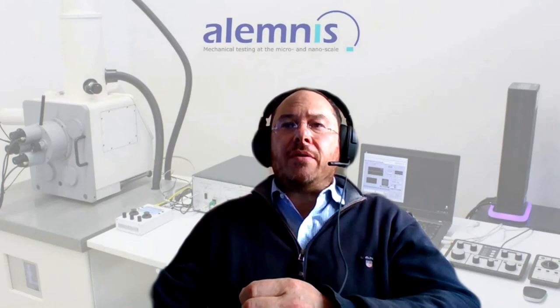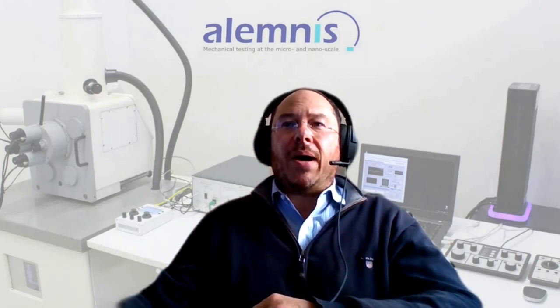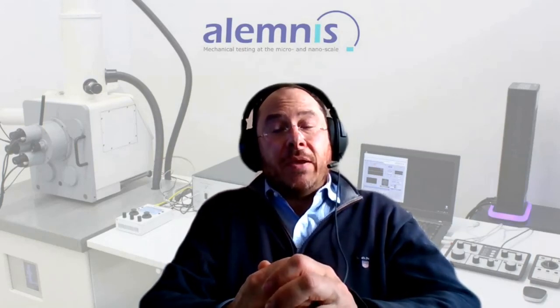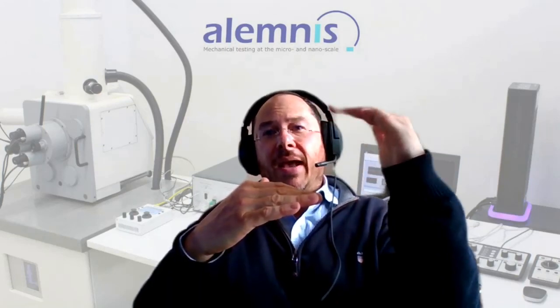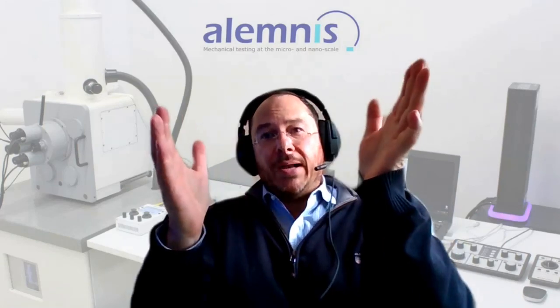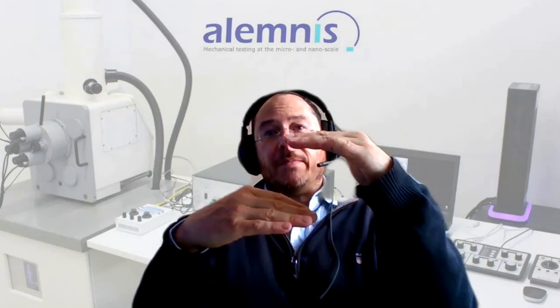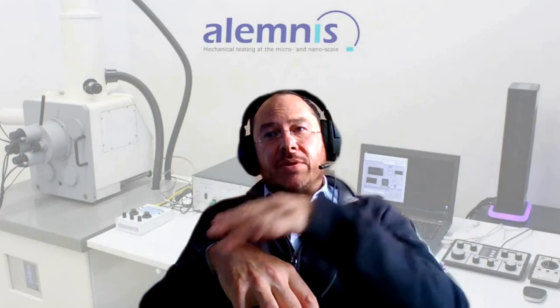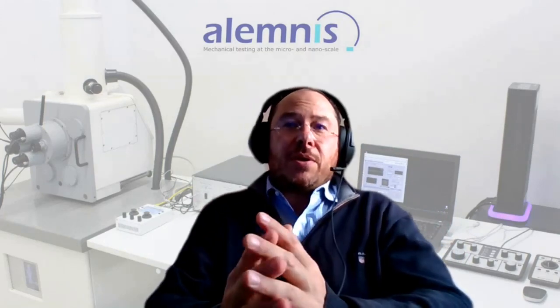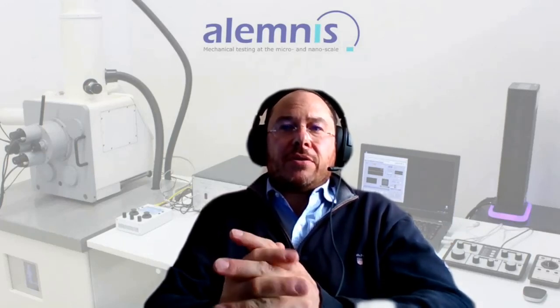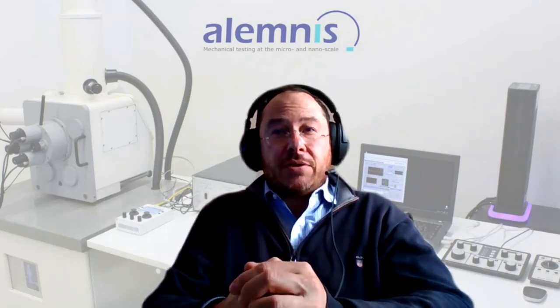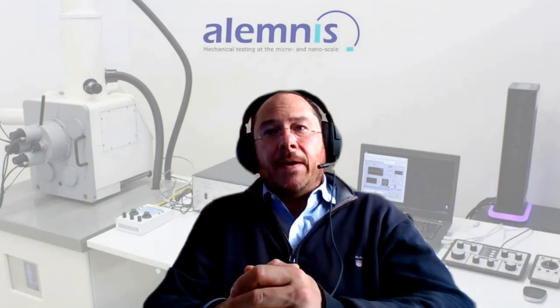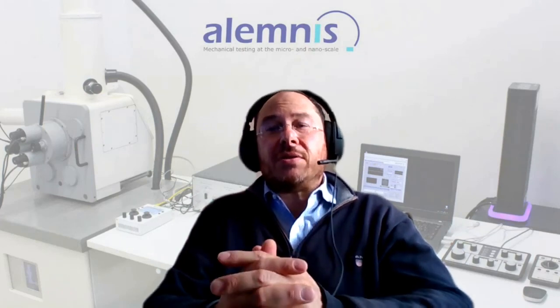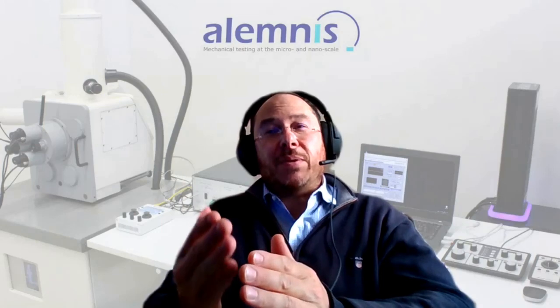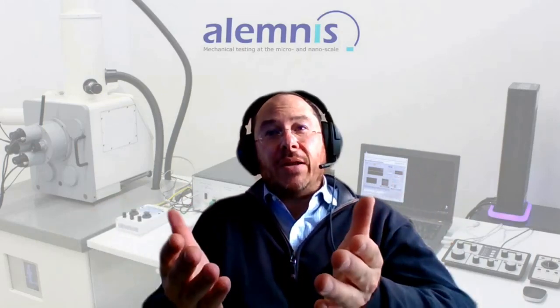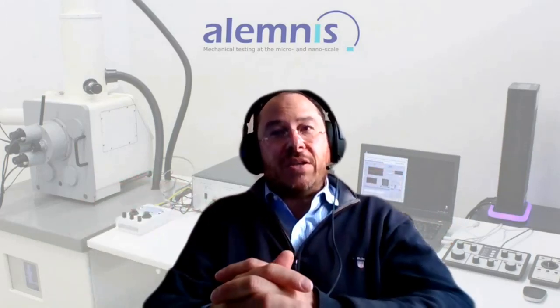There's another question here. Please explain the depth limit of coating for determining hardness without pileup. So this really depends on the type of coating that you have. If you have a soft material on a hard substrate, then any depth of indentation is probably going to cause quite a lot of pileup. If you have the opposite, let's say a hard coating on a soft substrate, then you can probably go relatively much deeper into the coating without having the pileup effect. So this question is really application specific. It depends on the two materials, the coating and the substrate themselves, and how thick the coating is. As a general guide, we try to keep the depth limit to about 10% of the coating thickness, but in many industrial applications, this is not possible. So we want our indentation depth to be deep enough to overcome surface roughness, but shallow enough not to have the effect of the substrate. So it's really a compromise depending on your particular material.